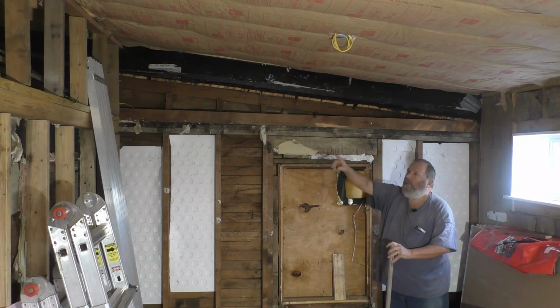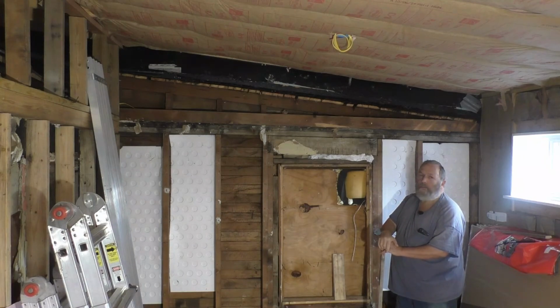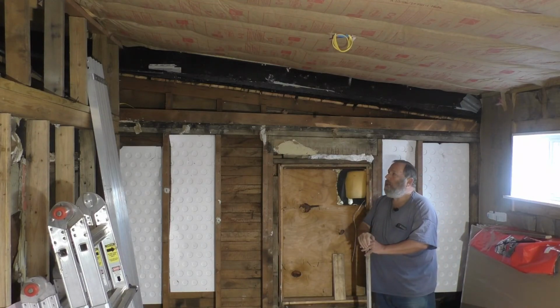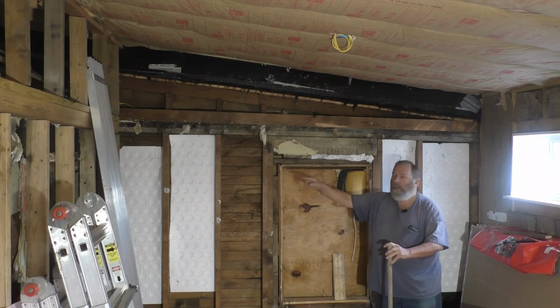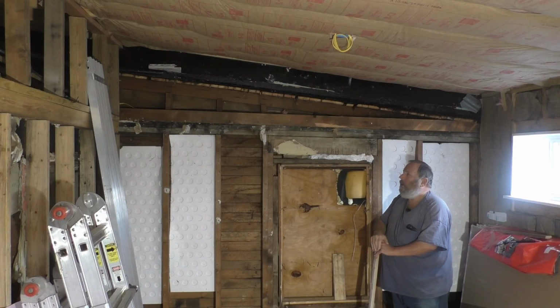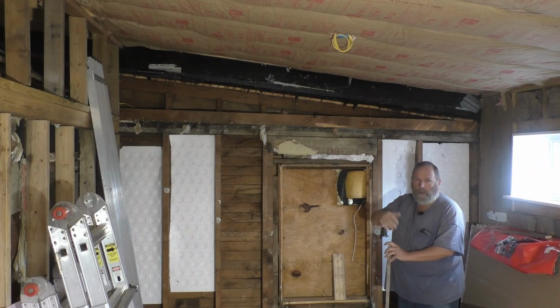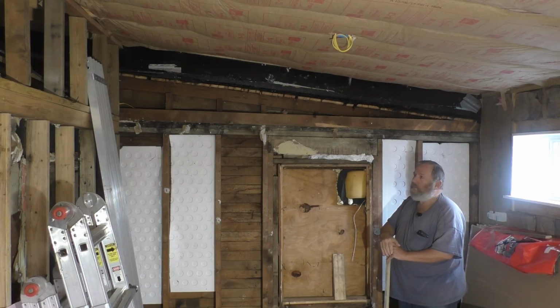Taking it up and around and back and through, that's a long run, and we may have volume problems. I know that in another part of the house, we have very little air, very low airflow coming out. It's probably because of the twisted way that the duct runs to that area. So I don't want to cause another problem like that here. Putting it in here gives a good airflow, and will help keep this room at the right temperature.